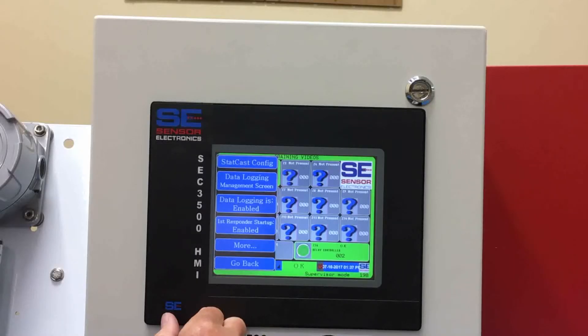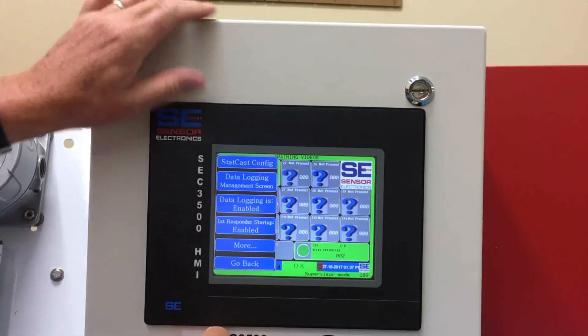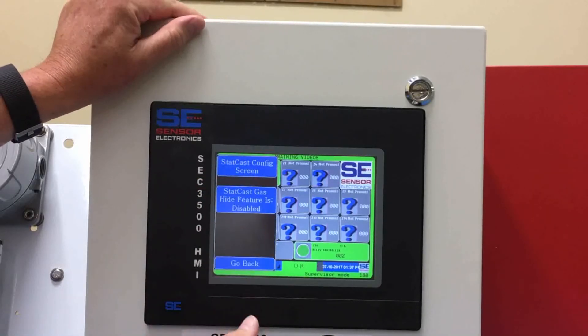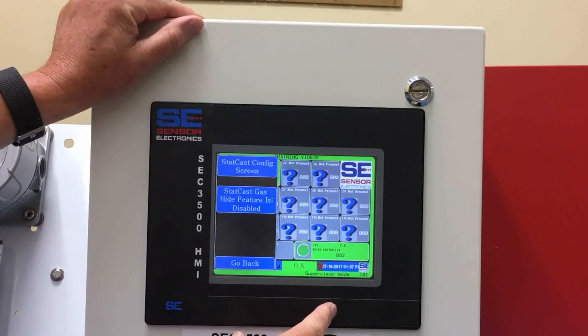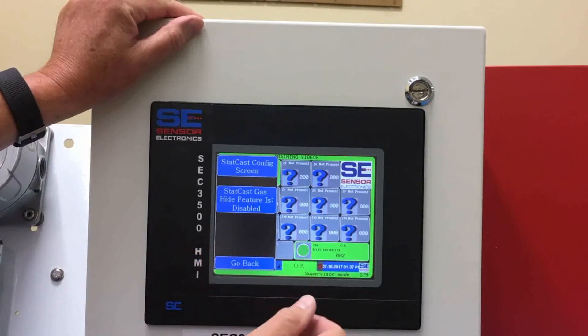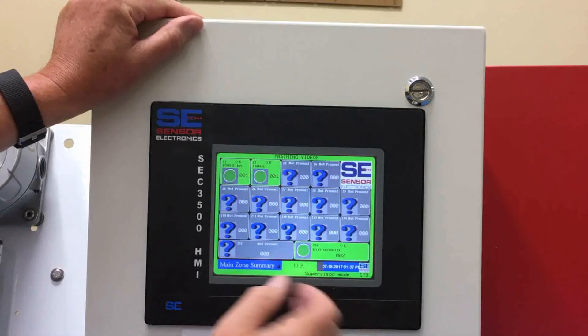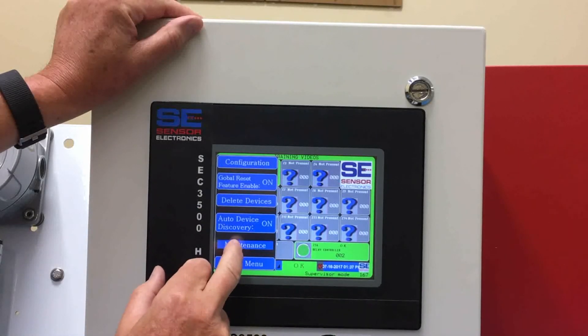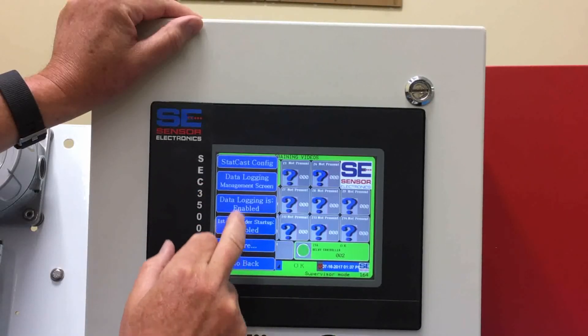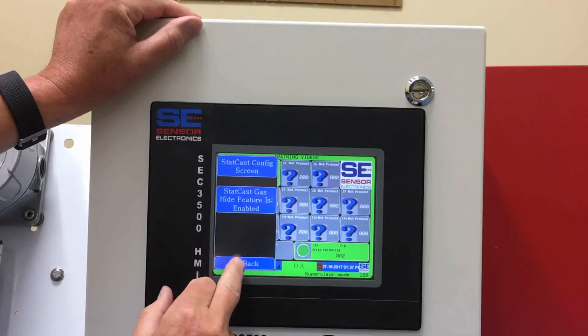More gets you into some more programming features. StatCast is another output that we have. The HMI 3500 panel has an RS-232 output which can continuously broadcast information in ASCII code. If you wanted to hook up to that, you'd enable it and then wire into the HMI panel. Once enabled, it would be continuously broadcasting out.